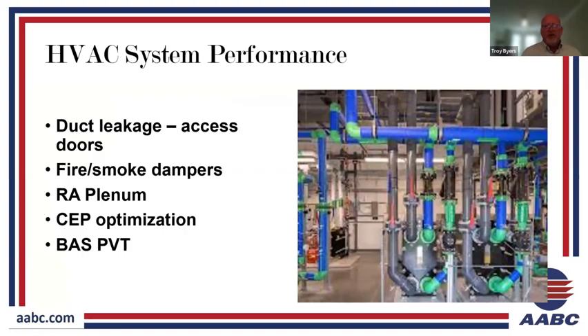And then other areas within HVAC systems that can impact performance, take an example here of duct leakage. Sometimes we see abandoned duct runouts that have not been properly capped or blanked off, or something has come loose that was previously applied to block an abandoned runout. We also have access doors throughout ductwork, let's say to access, for instance, a fire damper. Well, these fire dampers are also periodically inspected and tested. And so it might be that a door didn't get closed properly, or maybe a fire damper doesn't get reset.